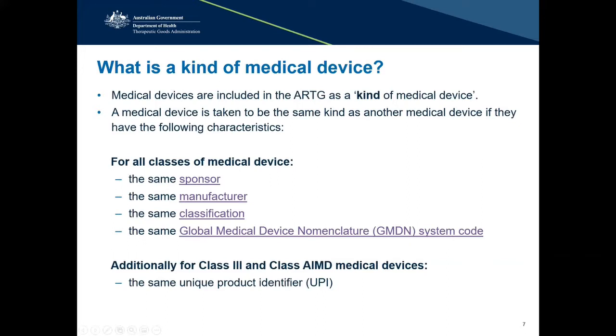So a sponsor is an Australian-based entity that's legally responsible for the importation, exportation, and/or sale of the medical device in Australia. And the application to include the device in the ARTG must be made to the TGA by the sponsor. And the sponsor must ensure and be able to demonstrate that the device meets all applicable requirements for safety and performance.